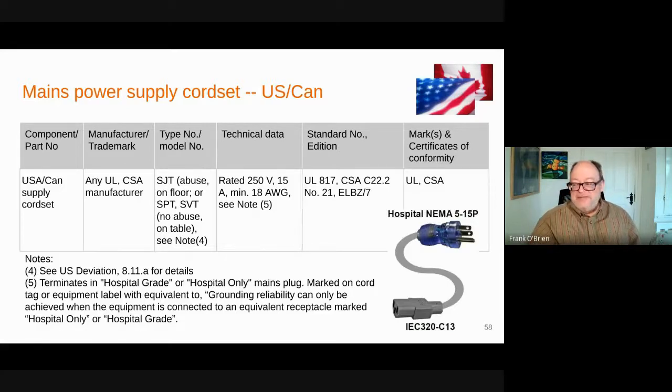So maybe you don't have to argue that if it's detachable, but it is rated that. But say you take a different approach that, well, of course, if it's for use at 240, they're going to have a different cord set. The plug's incompatible with 240 for North America, so they'll have to get a cord set for the compatible socket.